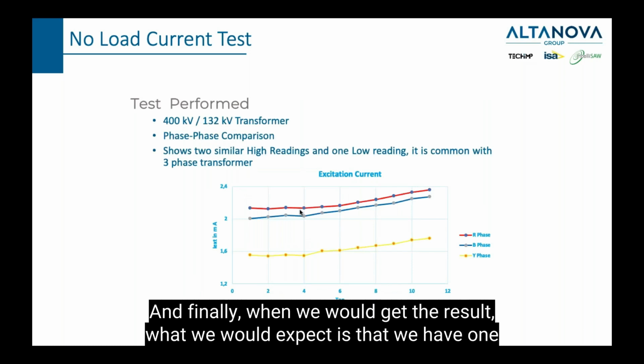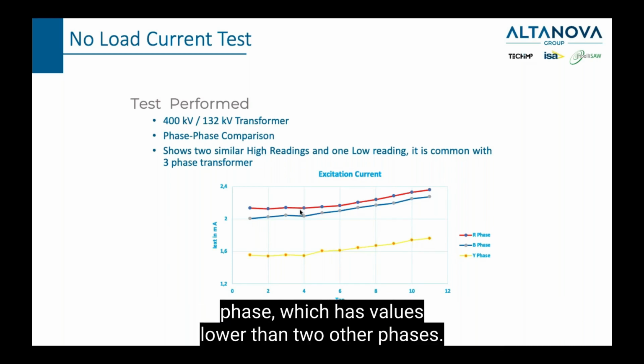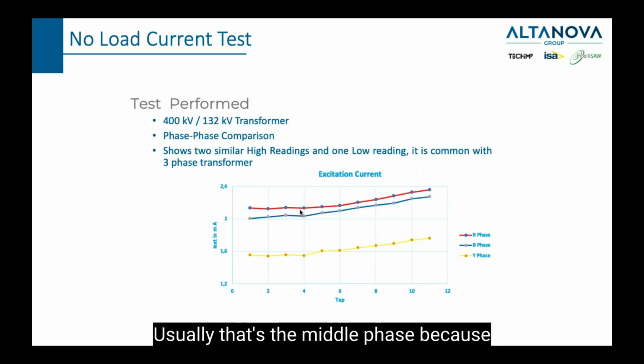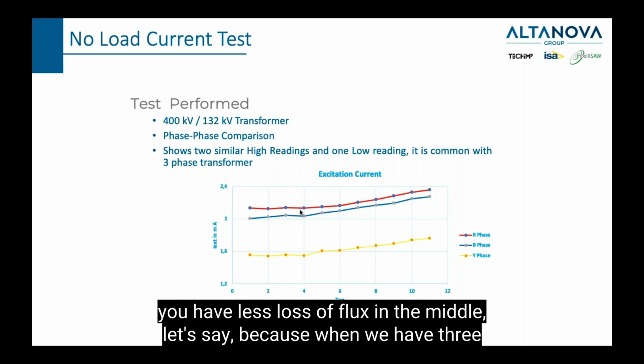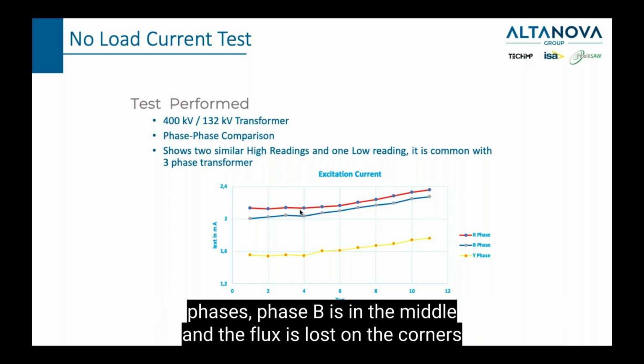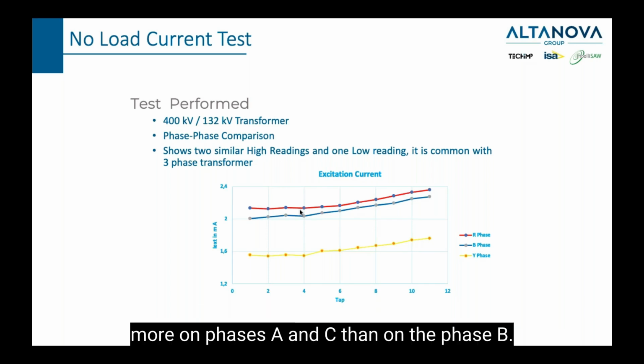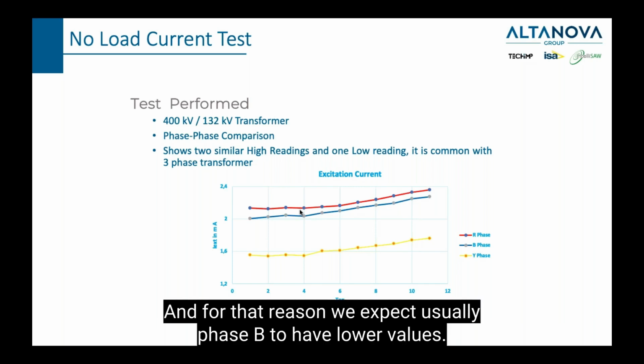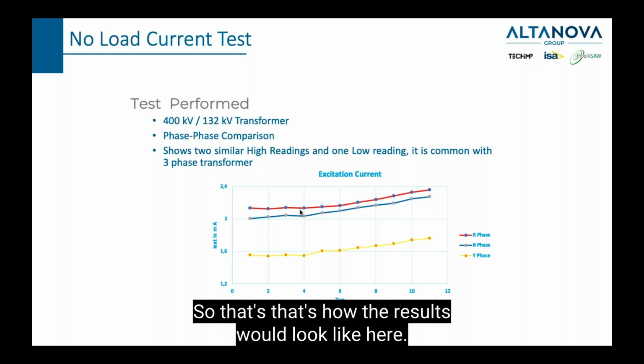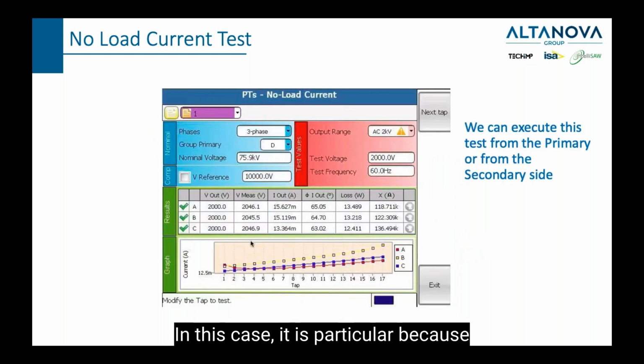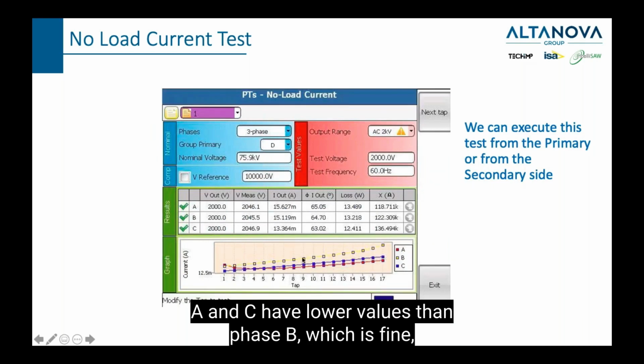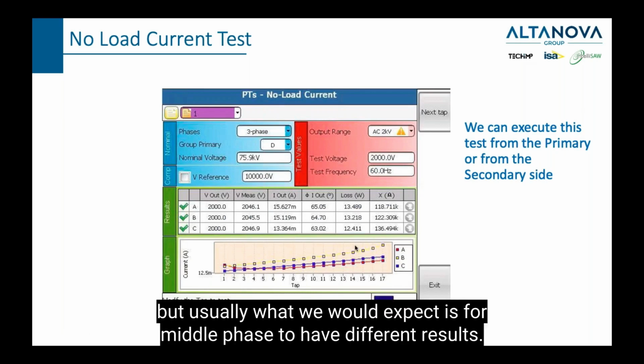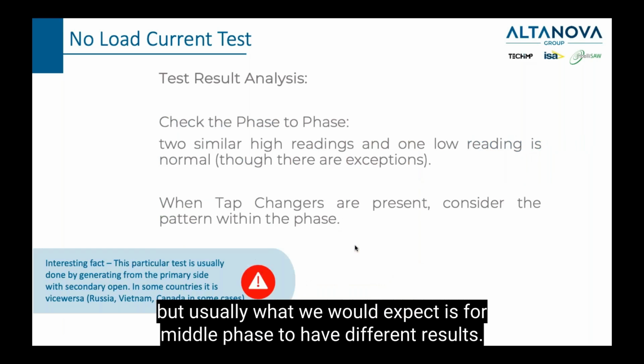And finally, when we get the result, what we would expect is that we have 1 phase which has values lower than the 2 other phases. Usually that's the middle phase because you have less loss of flux in the middle. When we have 3 phases, phase B is in the middle, and the flux is lost on the corners more, on phases A and C than on phase B. For that reason, we usually expect phase B to have lower values. So that's how the result would look. Here, in this case, it is particular because A and C have lower values than phase B, which is fine, but usually what we would expect is for the middle phase to have different results.